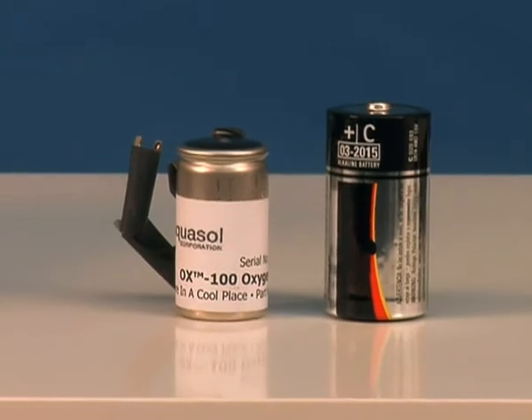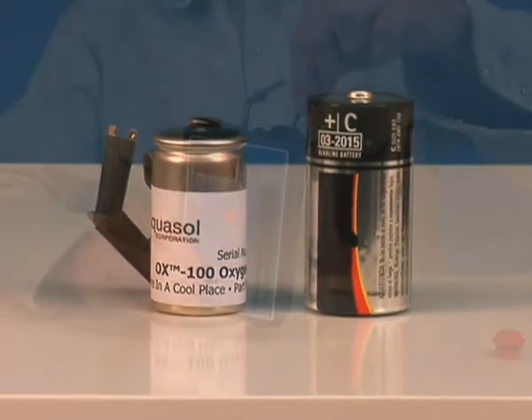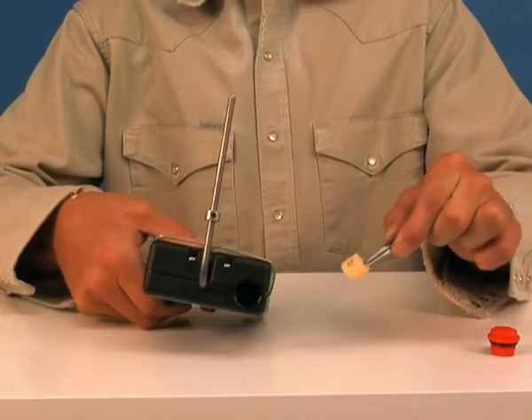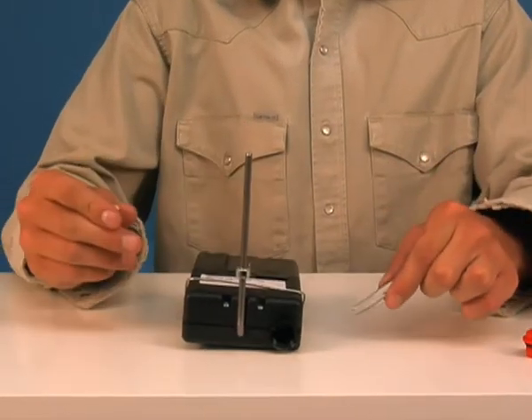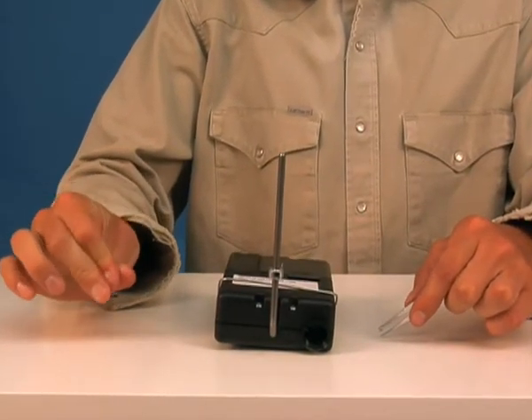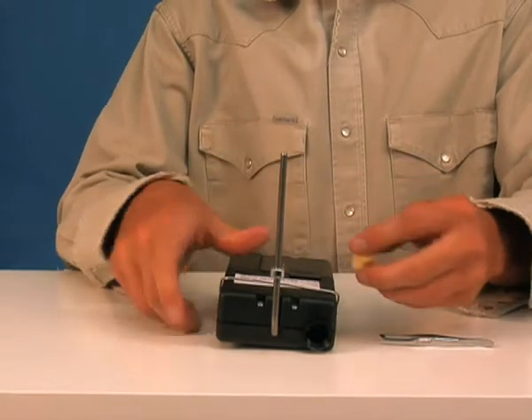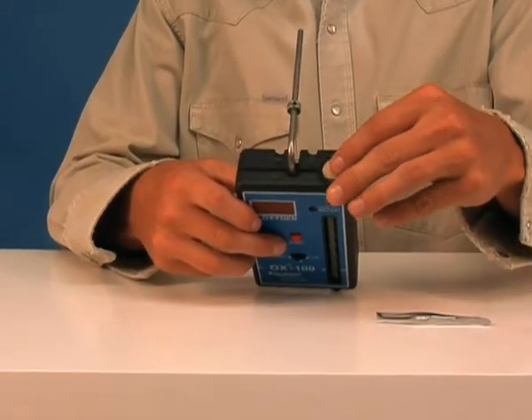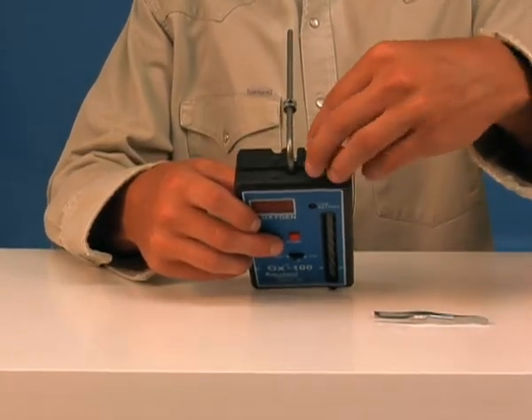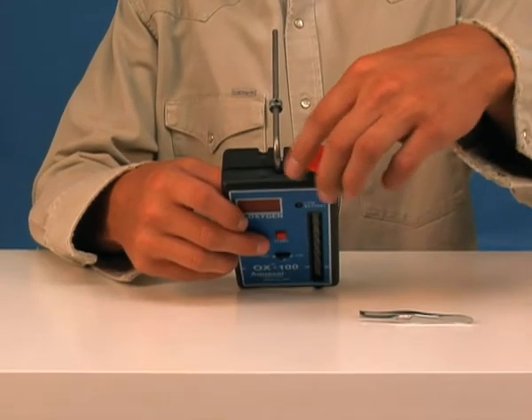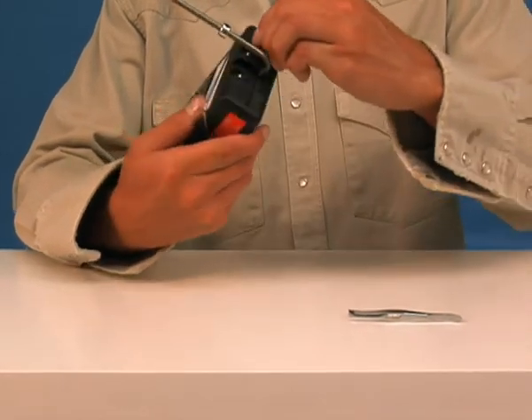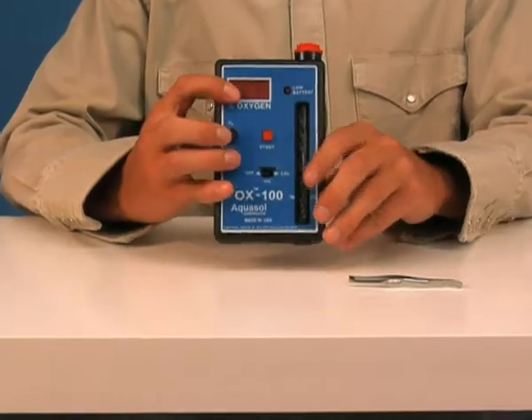To prolong the life of the oxygen sensor, moisture should periodically be eliminated from the sponge filter. To do this, simply squeeze the sponge anytime it is noticeably saturated. This will vary with the moisture content of the sample and initially should be checked every 20 samples. The sponge filter may be washed in ordinary soap and water. Be sure to thoroughly rinse and dry the filter before reinstalling it.